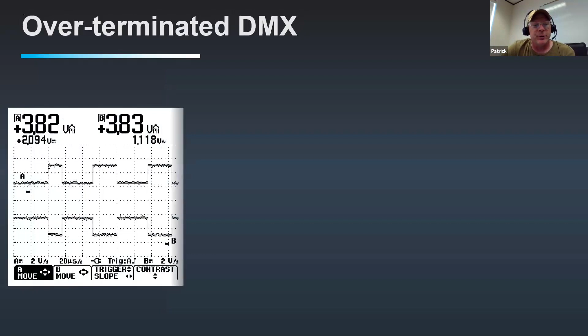So over termination can be a thing. Opto splitters and some lighting fixtures have termination switches on the outsides. Dimmer racks have terminator switches on the outside too. And if you turn too many of them on that string, you will bring the amplitude of the signal down.